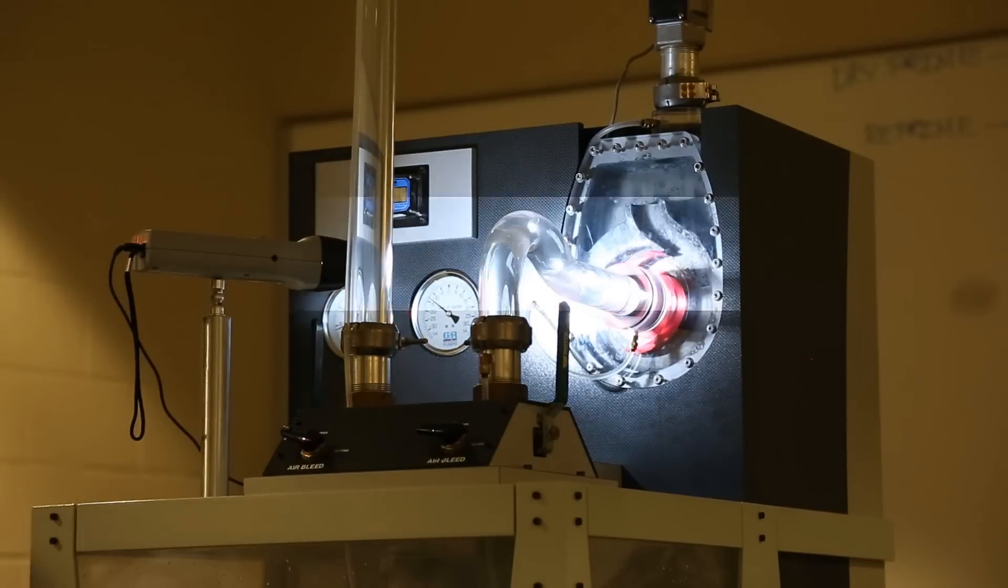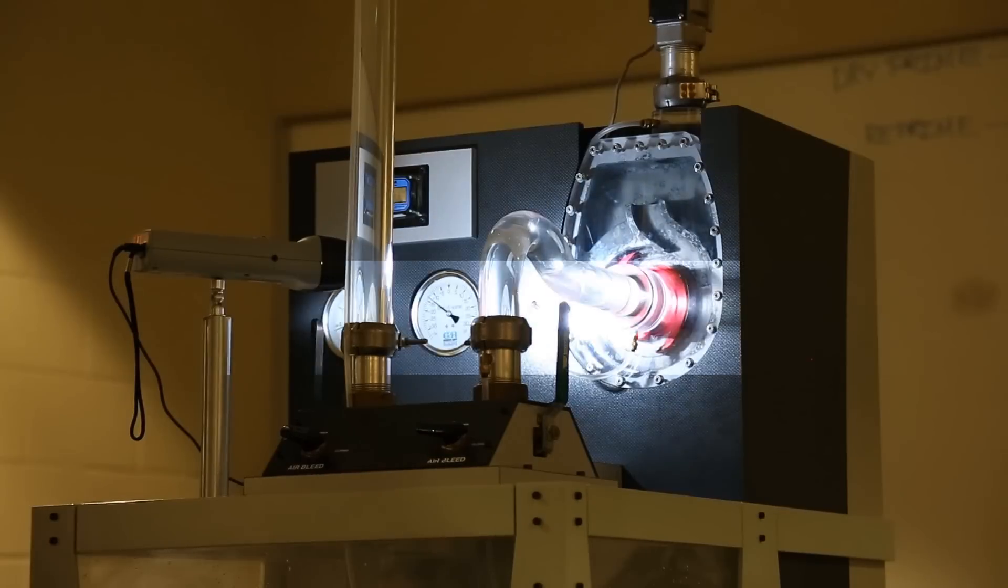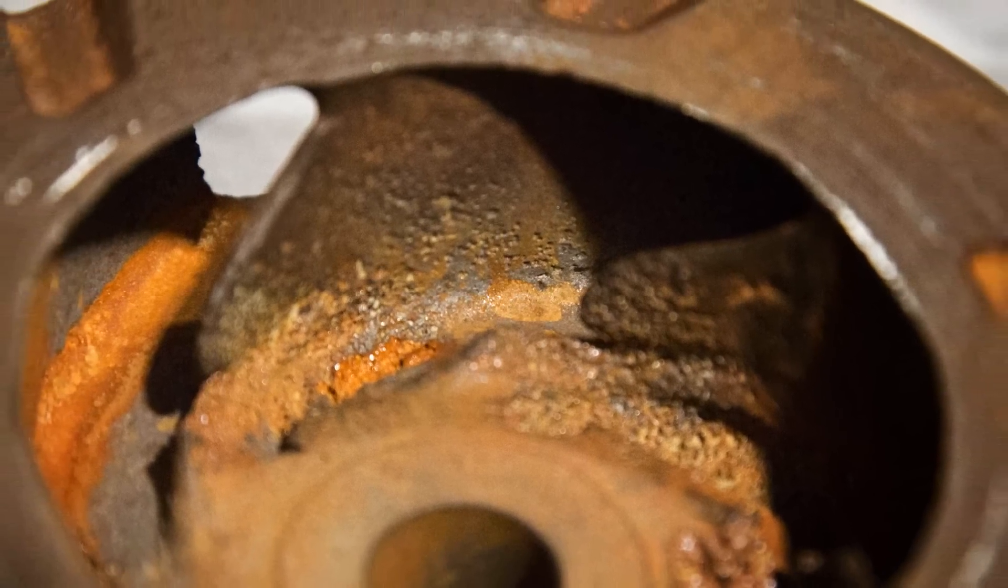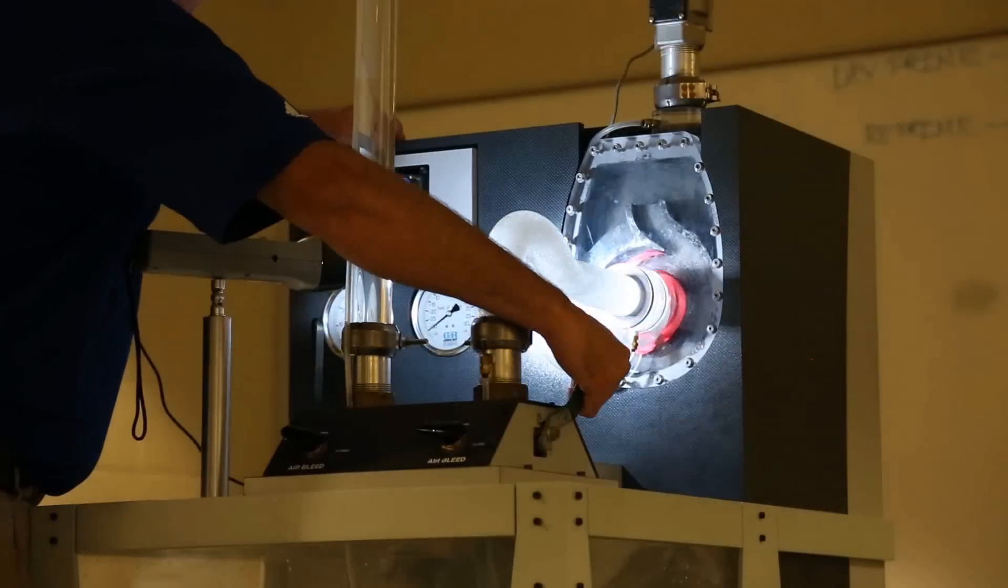The tensile strength on a ductile iron impeller is nowhere near that. So what happens is you start to blow away chunks of metal at the eye of that impeller.